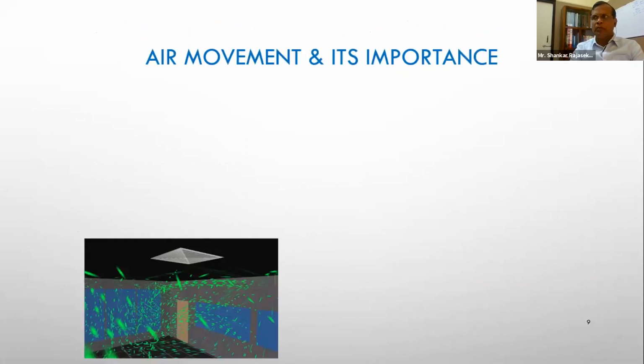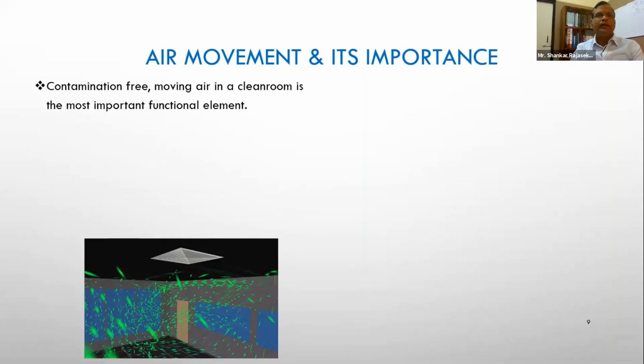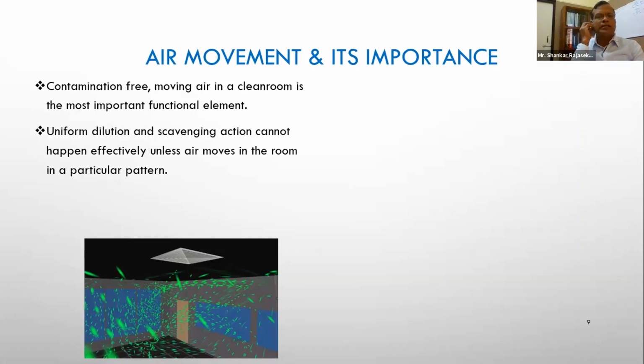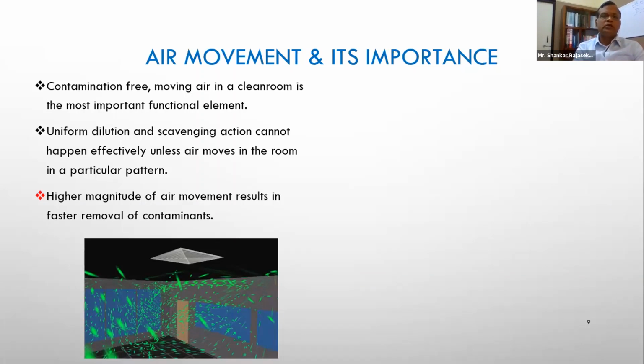So air movement. Air needs to keep continuously moving. If the air gets stratified, it becomes a place where the contaminants will build up. So contamination-free moving air in a clean room is the most important functional element. Uniform dilution and scavenging action cannot happen effectively unless air moves in a particular pattern in the entire room. So higher magnitude of air movement results in faster removal of contaminants.